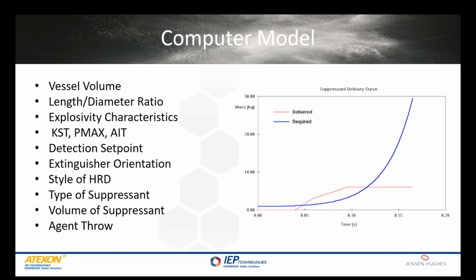What pressure you have your detection set at will have an effect. Even the orientation of an extinguisher, whether you're discharging vertically or horizontally, will have an effect. The type of suppressant, the efficiency of the suppressant, how far you have to throw the agent. If you have to use an extinguisher to put out an explosion that's 3 or 4 feet away, that is a different animal than if you have to put out an explosion that may be 12 or 16 feet throw for that extinguisher. So it's really important that explosion suppression systems take these parameters into account, and typically a computer model is used so that you can get an output to determine the efficacy of a system design.